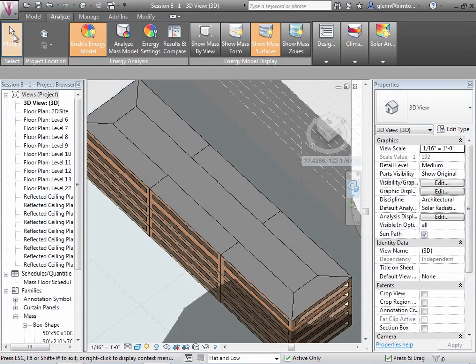at a very high level, this is the way, by default, it's thinking of dividing up your model. As a first level assumption, it's probably not too bad. It's divided things up into 5 different floors. These are windows based on some percentage that it put in there automatically, and we'll adjust that in a second. Up here at the top, you're seeing the zones. Things that are close to the window behave differently thermally than the things in the core of the building. That's typically true, even in this building. The offices are about 10 or 12 feet deep, and then you hit an interior partition where what's happening in the inner core is a little different than what's affected by the window. So it wants us to consider those a little bit separately.